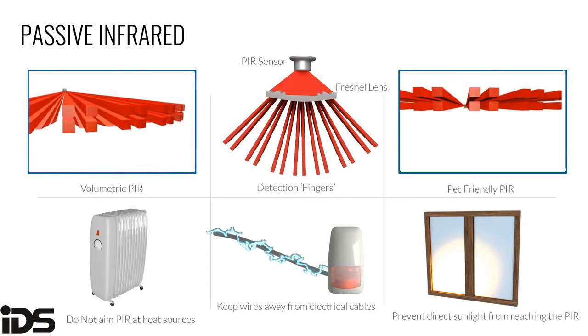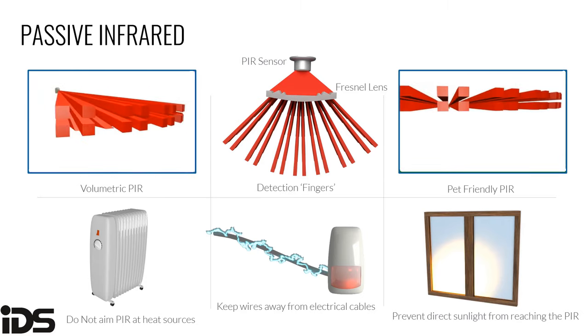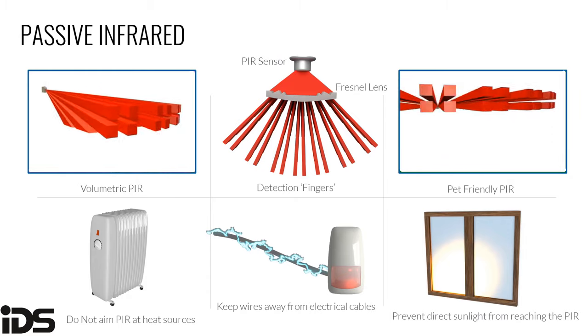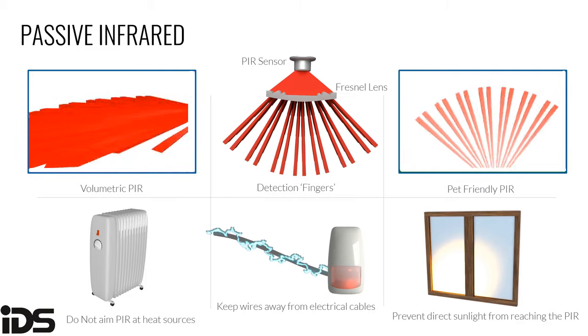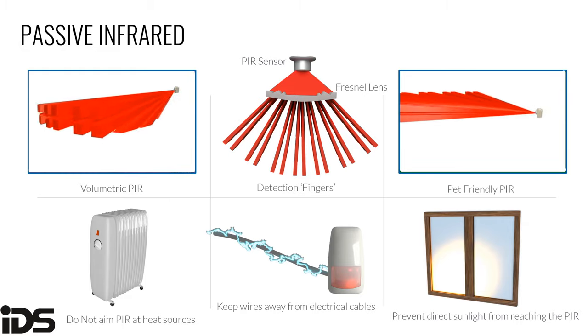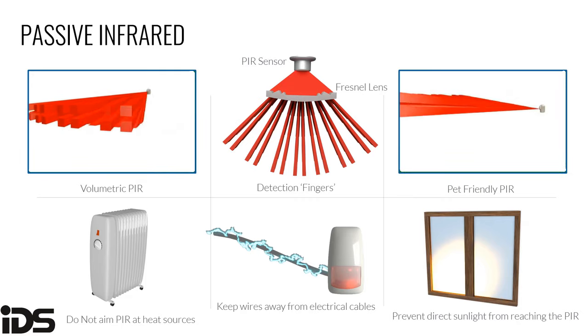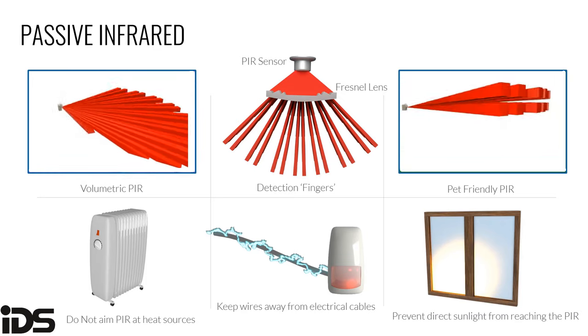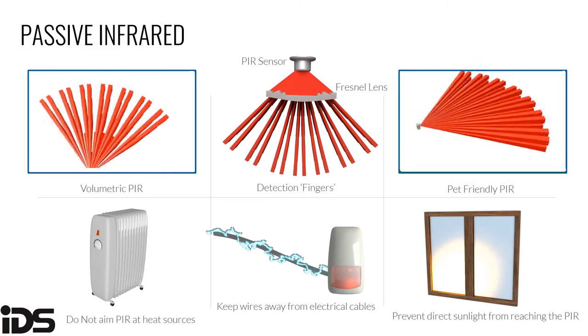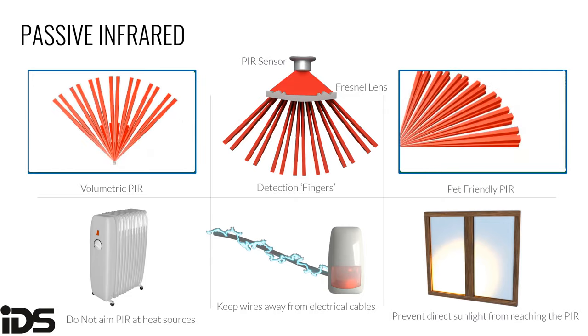A common helpdesk call involves a detector false-alarming at around 6:30 in the morning or evening with no one present. Investigation often reveals the detector is facing east or west — toward sunrise or sunset. When a cold morning sun rises and hits the detector directly, it can cause a false alarm because the PIR detects the sudden temperature change. You may need to be creative with placement — try facing the detector toward a perpendicular wall rather than directly toward where the sun rises or sets.